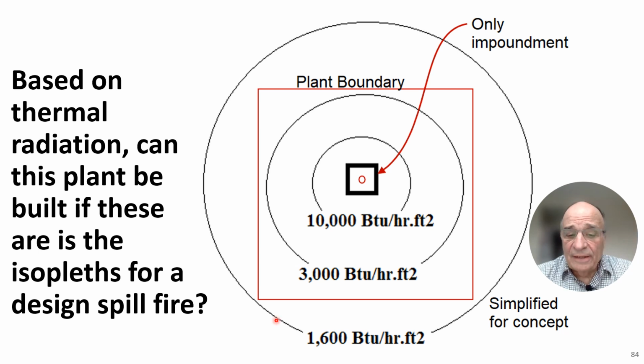Take a look at it, and we see there's 1,600 BTU outside the property line. That's 1,600 BTU per hour per foot squared. And the question now is, can this be built upon? Can this LNG plant be built by code? The question really determines whether this is land that can be built upon. If it is, then this cannot be cited as acceptable, meeting code requirements, because you could build a building here, you could build a building here, etc.